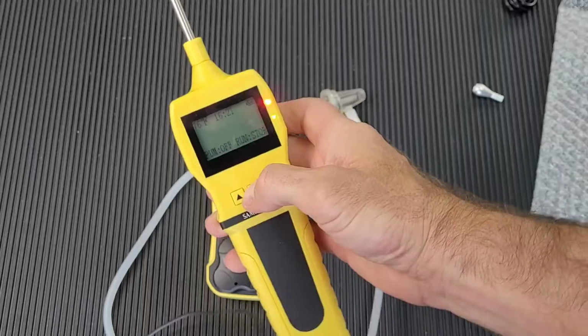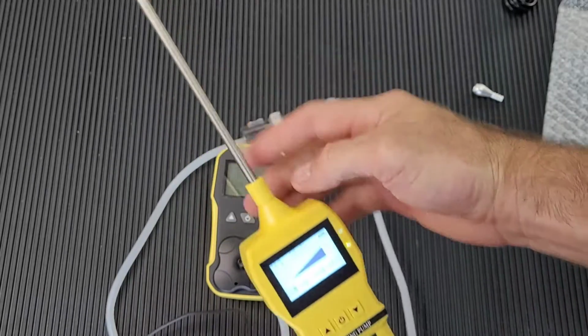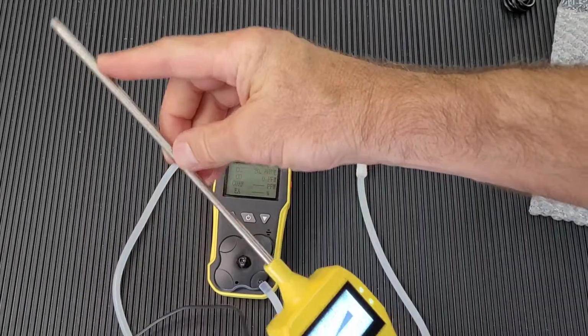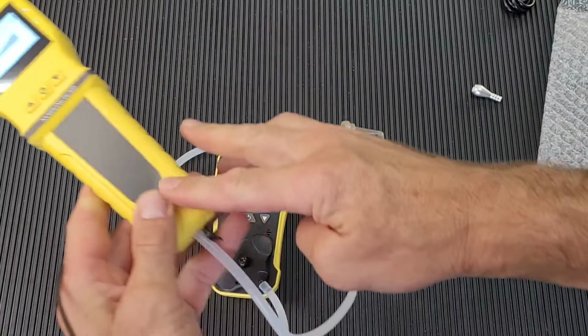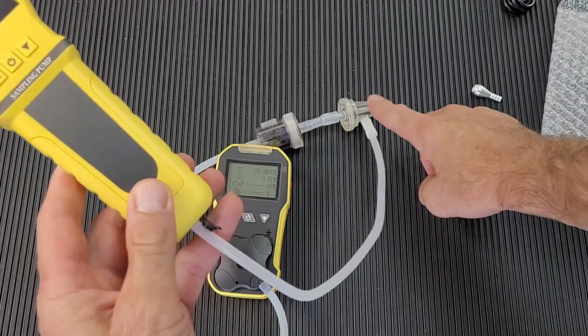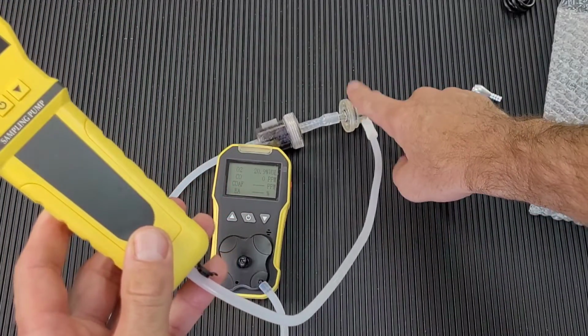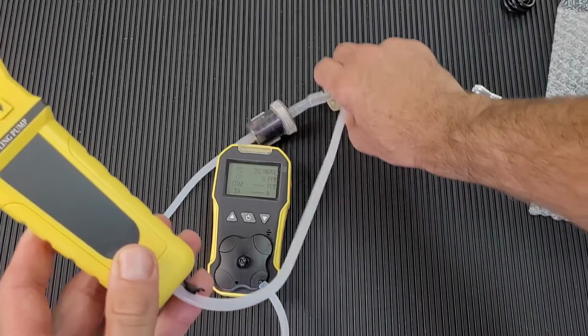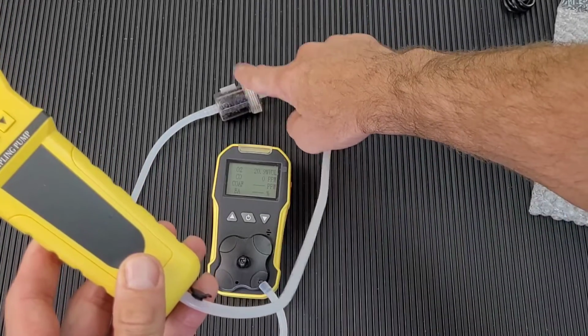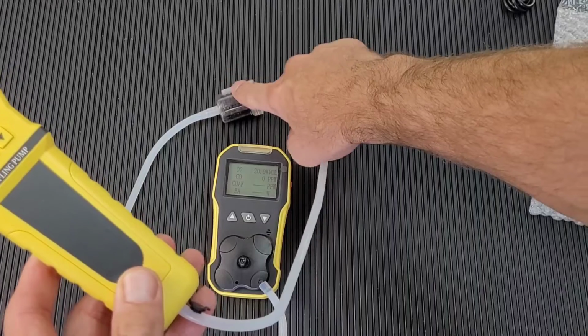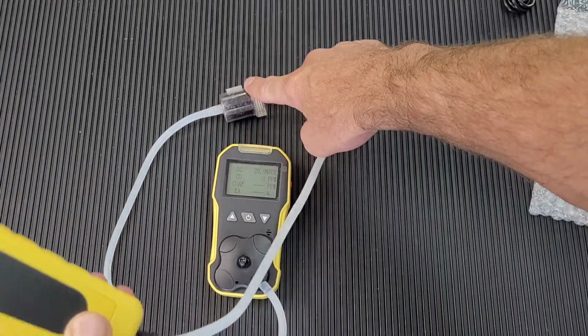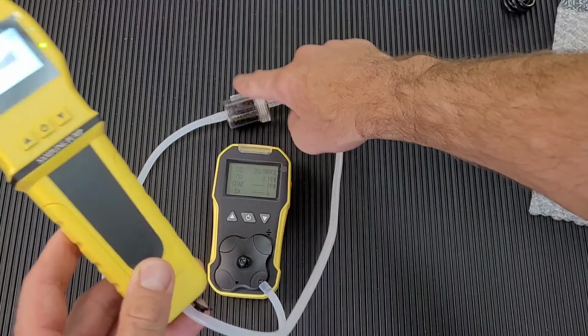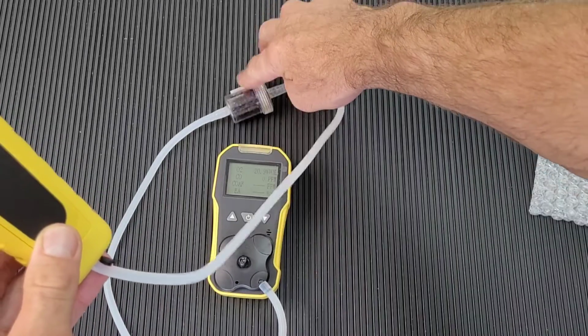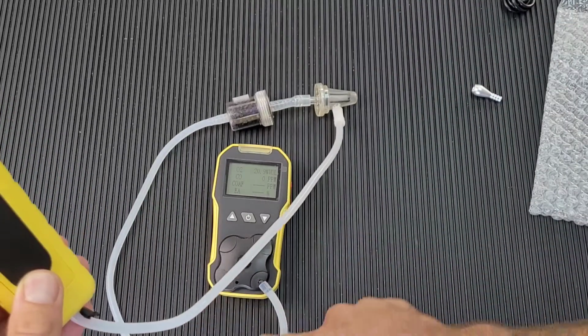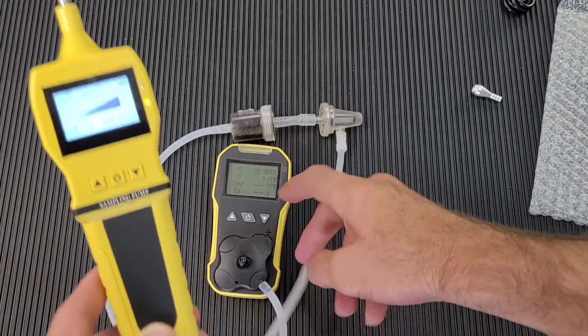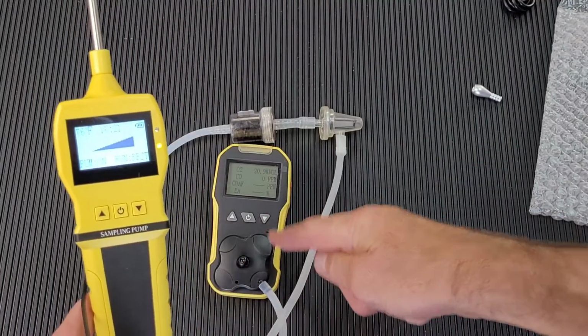So let's repeat what's going on here. We have a pump. You're going to pop this in the flue. Air gets drawn through the pump, through the tubing, into the water trap. If there's any condensation, it'll get trapped over here. Any oxidizing gases will get trapped into the charcoal and the pebbles over here to soak up all the moisture, and further goes onto the sensors. Okay, folks, so that's the setup. Air through and then onto the analyzer.